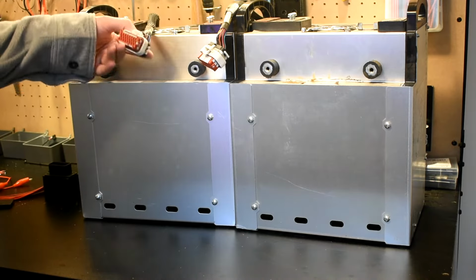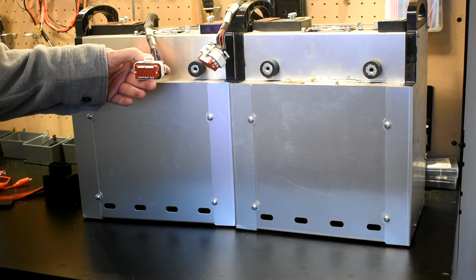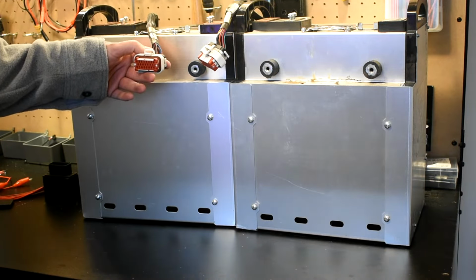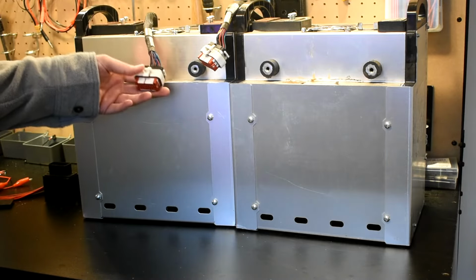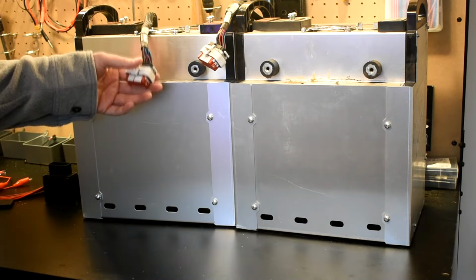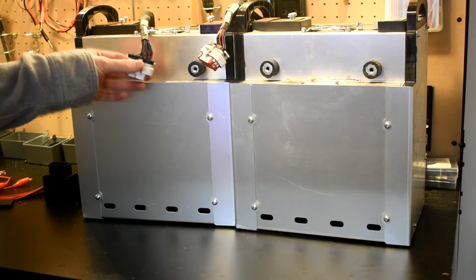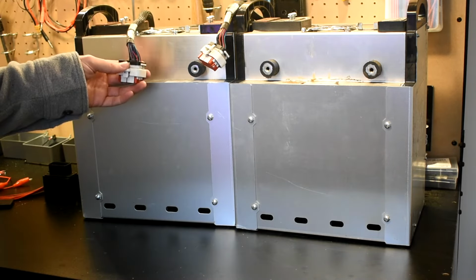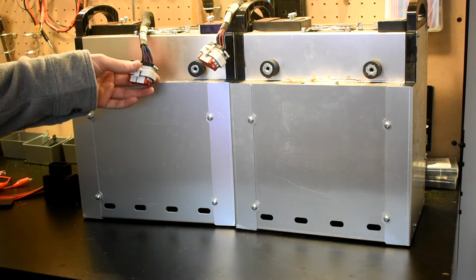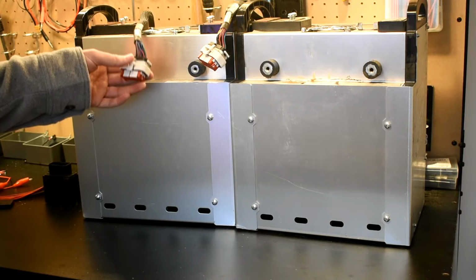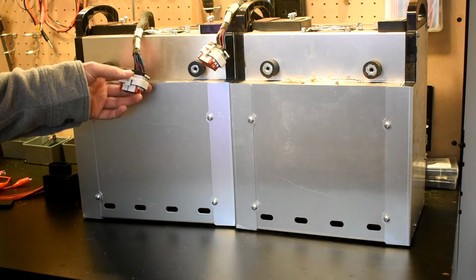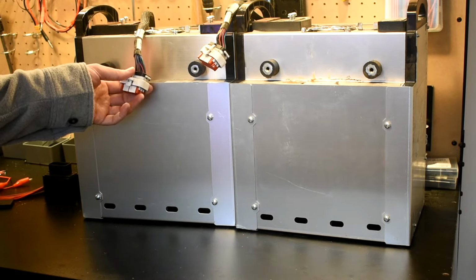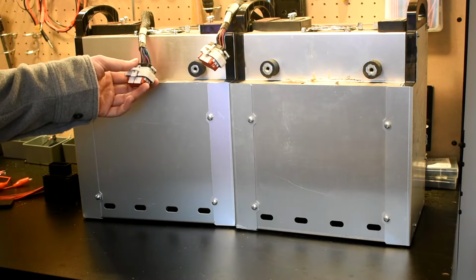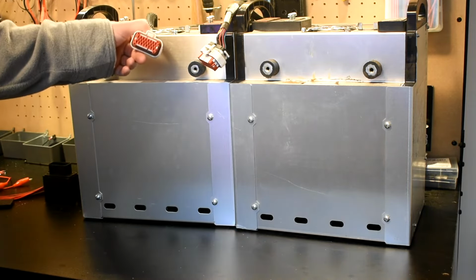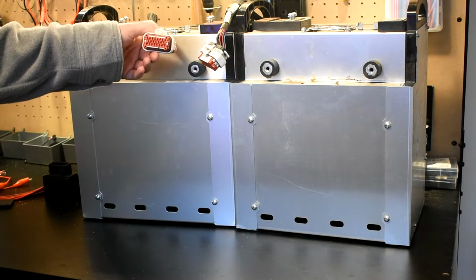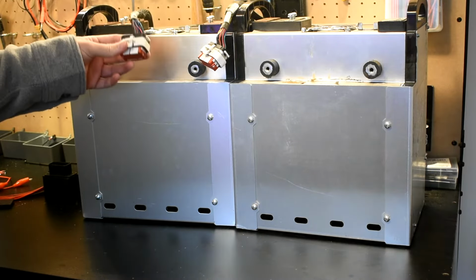We'll be using these lead wires in these bundles for our BMS leads, and we won't have to cut the wires. I have connectors we'll show in a second, but you can cut them if you want. Warning though, if you just go into this bundle with wire cutters you may create a short and burn something out. Be very careful, cut one wire at a time, and insulate that wire before moving to the next. There are only 8 or 9 hot pins in here, but still, be careful if you do it that way.